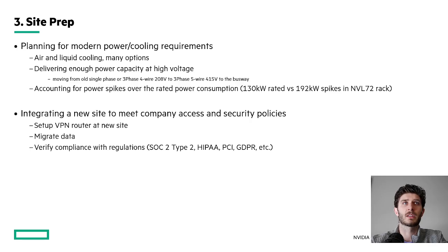Air and liquid cooling has many different options, and a lot of our customers are moving from old single-phase or 3-phase 4-wire 208-volt to the new modern 3-phase 5-wire 415-volt power delivery to the busway. They're also having to account for power spikes over the rated power consumption, where, for example, an NVL72 rack, though rated for 130 kilowatts, can spike to 192 kilowatts in real, measured power consumption.